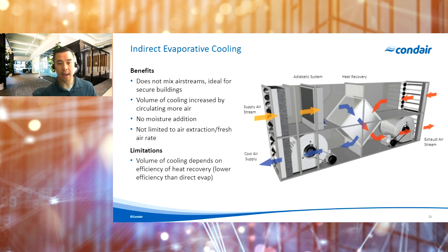Now, the other way that we can apply these is through what we would call an indirect cooling system. So in this case, the airstream is cooled adiabatically, with one of the systems that we've talked about, passed through a heat recovery system, then exhausted out. The supply airstream to the space, which can be recirculated from the space, is indirectly cooled from the other side of that heat recovery unit. So this allows for the supply airstream to be cooled adiabatically without adding moisture and eliminates the risk of any outside particulates or contaminants from coming into the space.